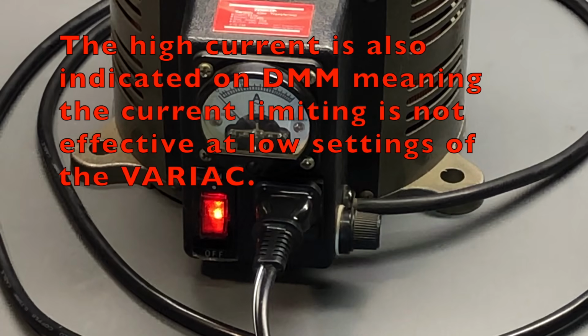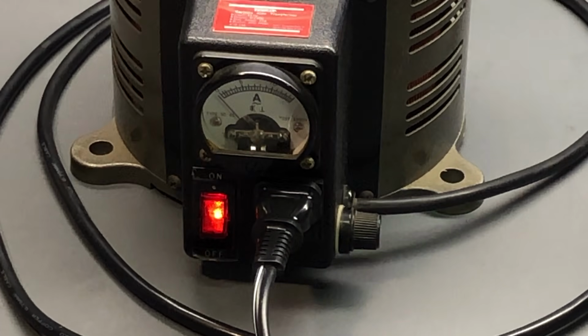So what does that mean? Well, this configuration is not the best choice because having the bulb first causes a problem of high current flow at low voltage settings of the Variac. That can pose a problem, with just excessive wear on the contacts of the Variac, and it's just not the best arrangement. Other configurations, as we'll go through, don't have that problem, and I'll demonstrate that shortly. So keep that in mind, that putting the incandescent lamp first has the negative effect of high current flow at low settings of the Variac, particularly when you have, or really only when you have, a very heavy current on the secondary, or a direct short for that matter on the secondary of the isolation transformer.